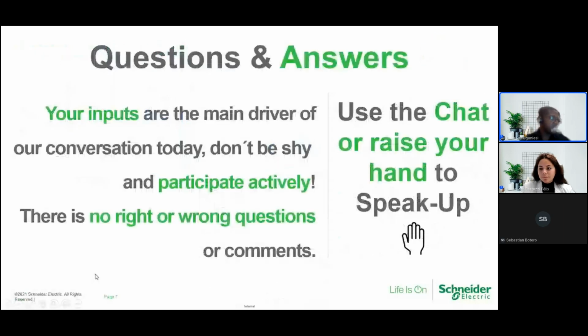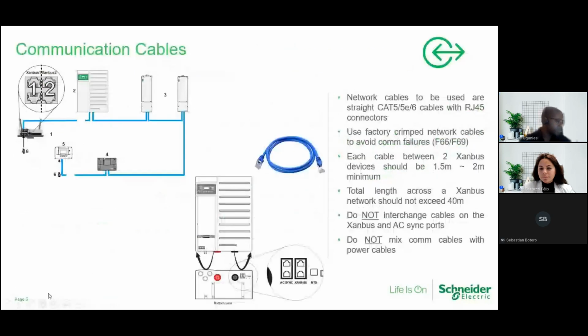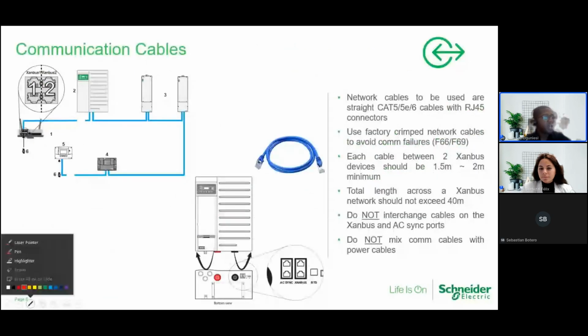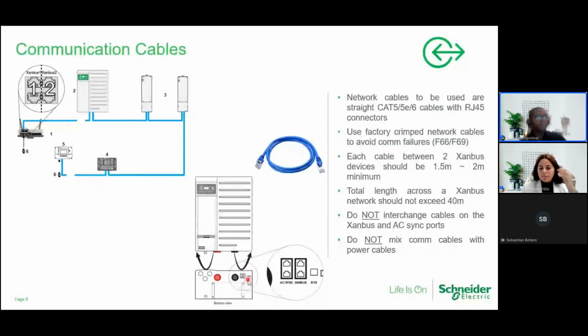At the bottom of the inverter, once you look under it or flip it, you'll see this portion - these are the communication ports of the entire system. You have your AC sync ports, your Xanbus ports, your battery temperature sensor ports, and to the right, slightly cut off, your auxiliary ports. For now, we'll mainly focus on the AC synchronization ports and the Xanbus ports.